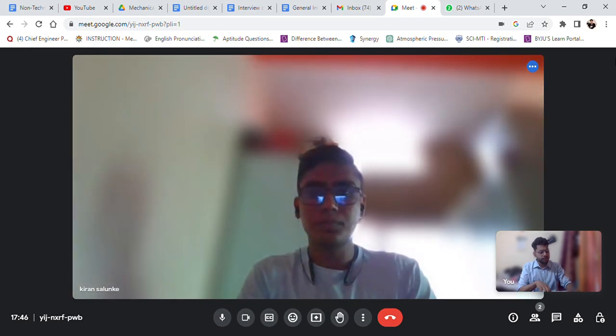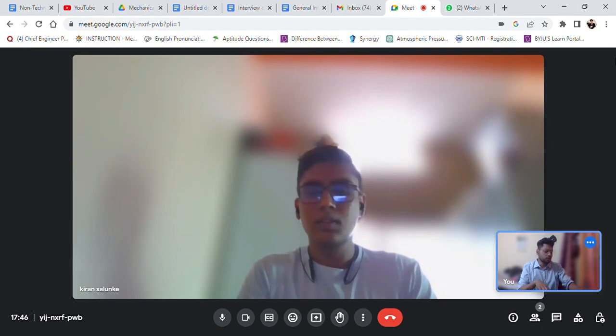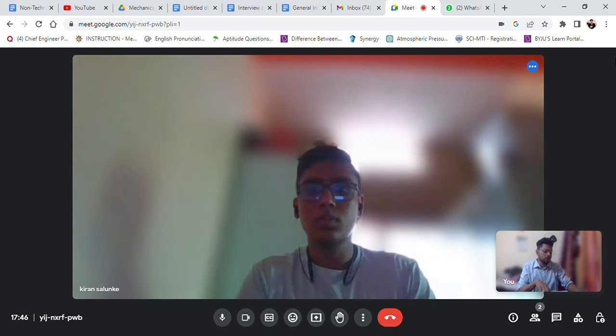Okay. What is the temperature of the evaporator coil generally? That is -18 to -20 degrees Celsius. And the condenser coil? The condenser coil temperature ranges between 40 and 45 degrees Celsius. Okay, Kiran.